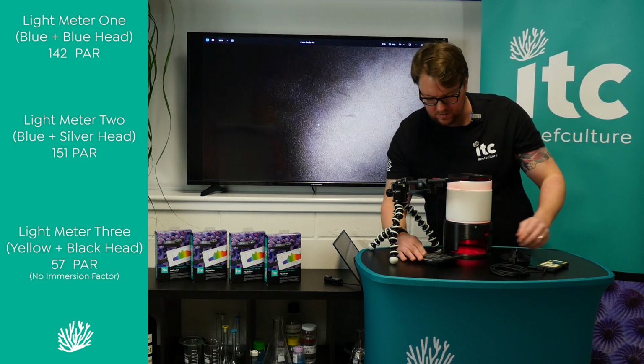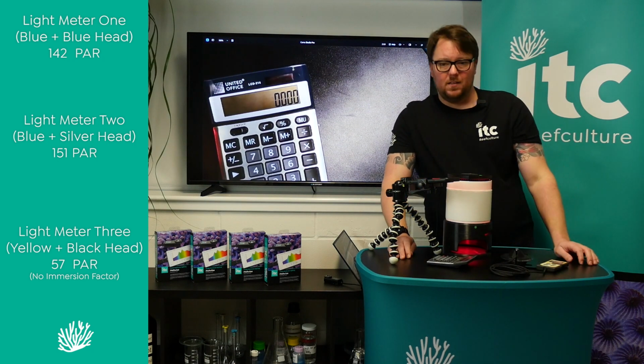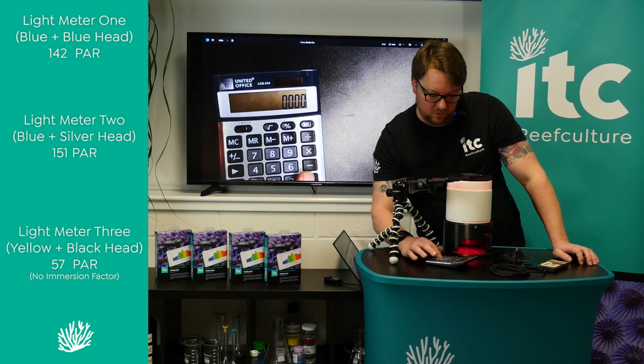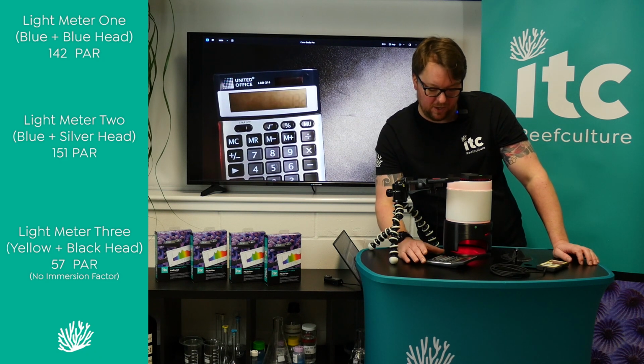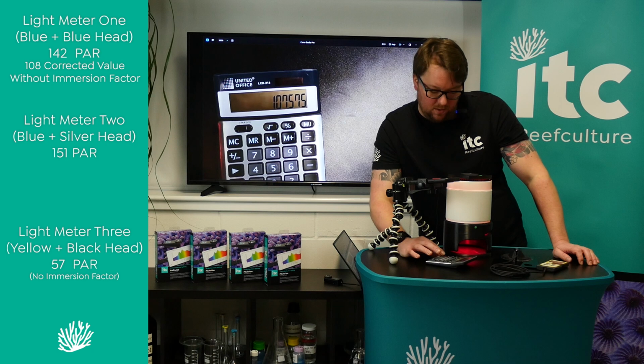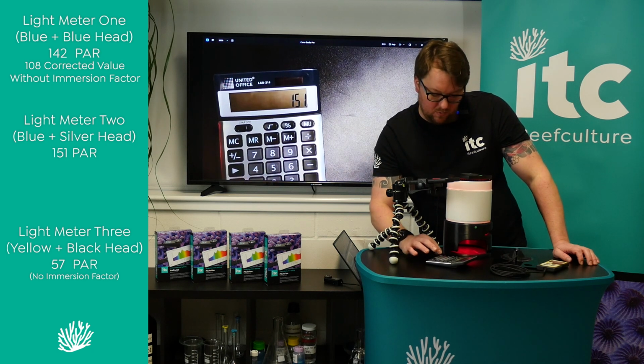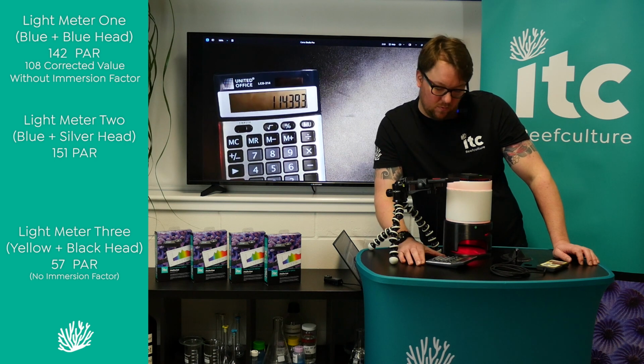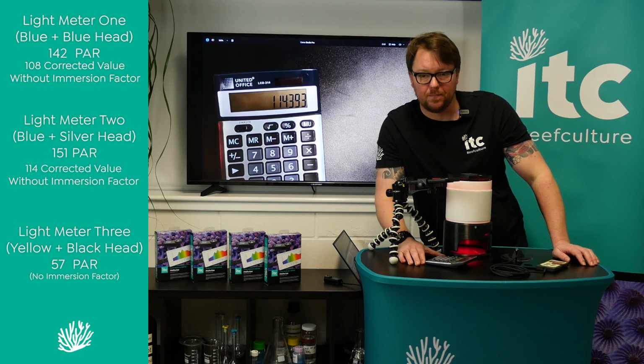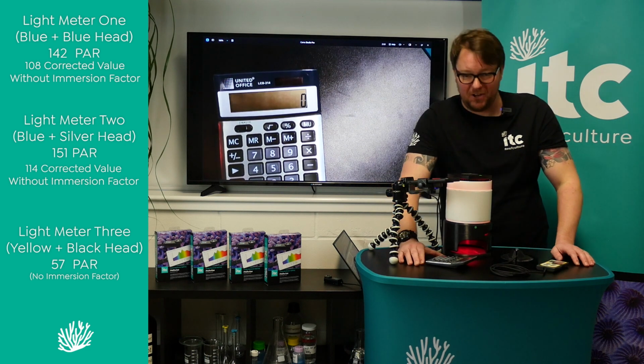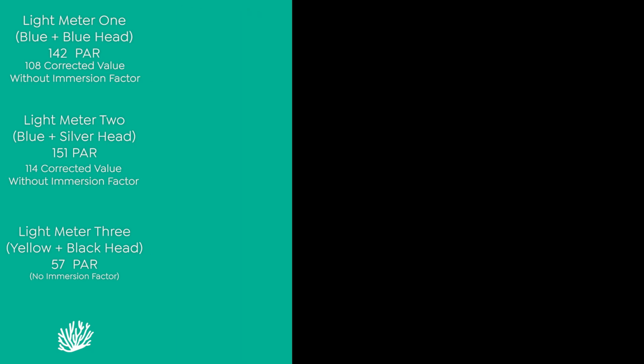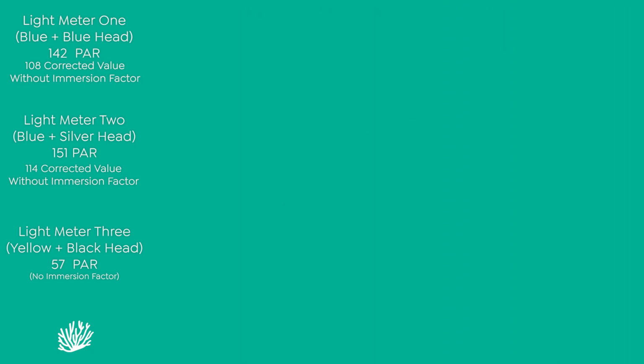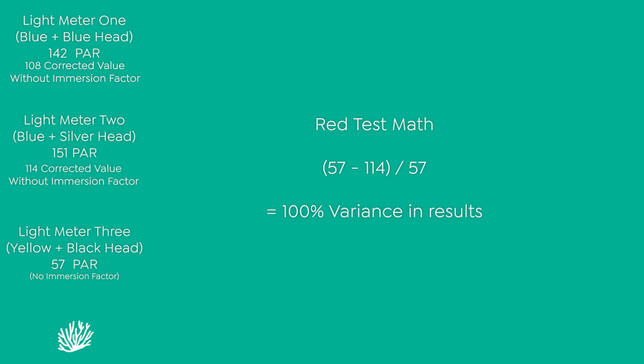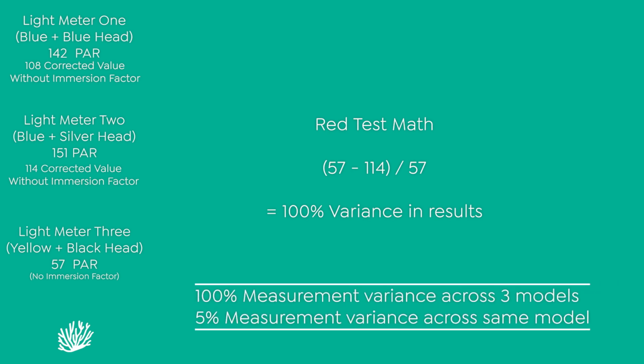So, let's get the calculator back out again. We're going for 142 divided by 1.32 to take the immersion correction factor off. And that's 107.5, so 108, let's call that. And then we have 151 divided by 1.32, and that is 114.39, so we'll call that 114. And then we're down to 57, so we're looking at 57 minus 114 divided by 57 equals 100% variance in the smallest and the largest measurement across those 3 meters.